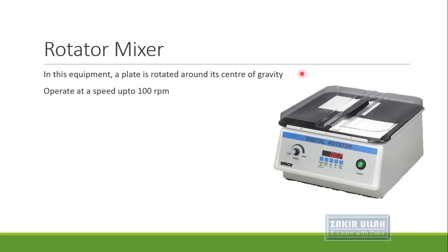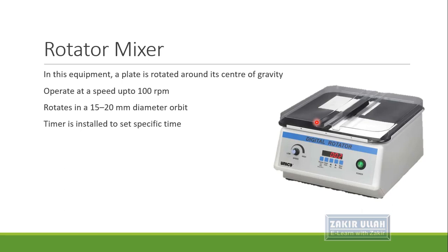The third type of mixer is the rotator mixer, in which a plate is rotated around its center of gravity. It can operate at speeds up to 100 RPM and rotates in a diameter of about 15 to 20 millimeter orbit. A timer is installed so we can set an experiment unattended for a specific time. It is supplied with a lid which helps prevent the drying of samples.